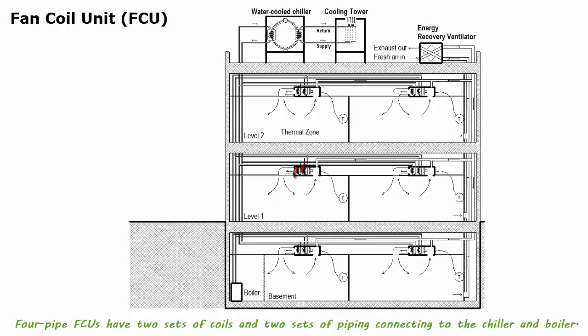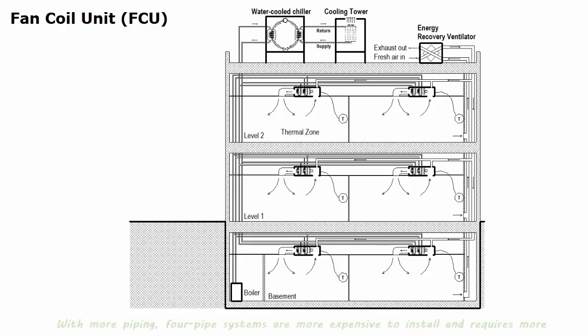Four-pipe fan coil units have two sets of coils and two sets of piping connecting to the chiller and the boiler. These systems can deliver cooling and heating simultaneously by using the chilled water and hot water coils at the same time, so that the building can be cooled or heated simultaneously. With more piping, four-pipe systems are more expensive to install and require more space to accommodate the additional pipes. The increased number of connecting points and valves also results in more maintenance.